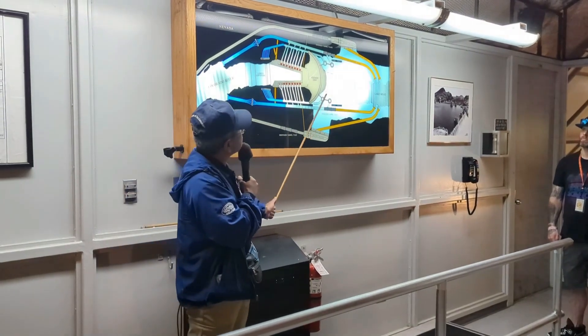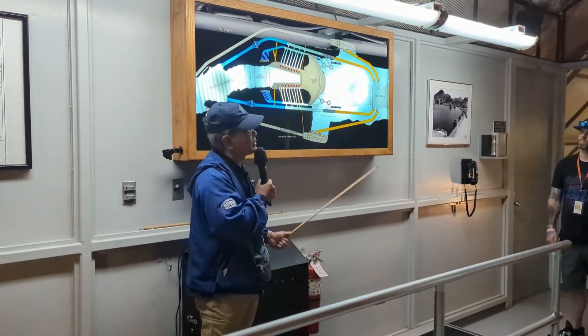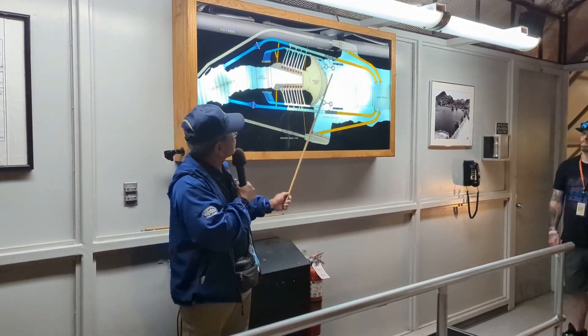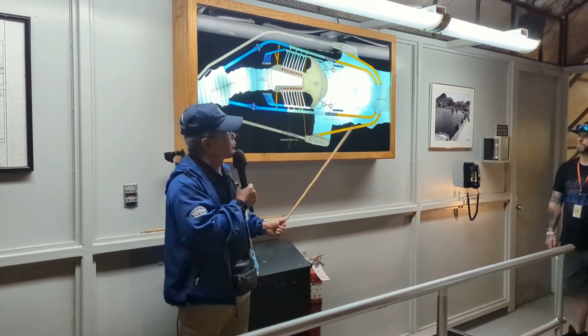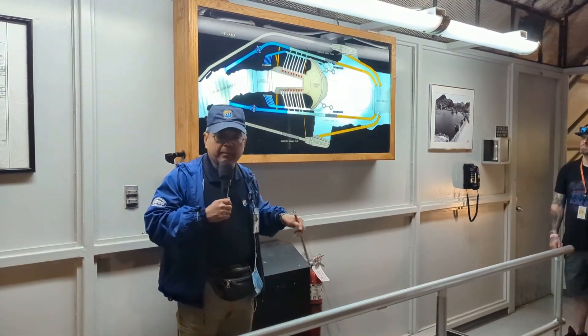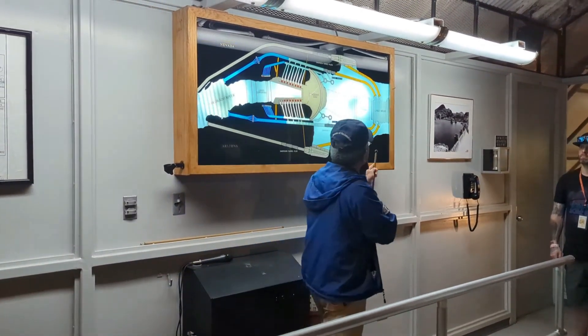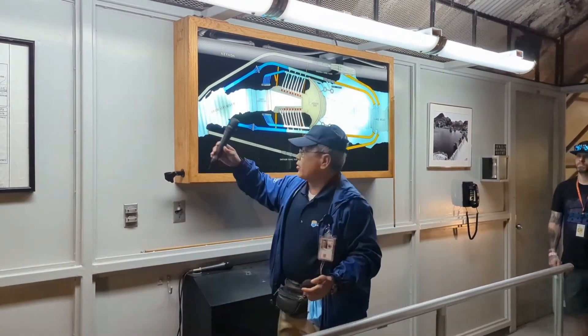The two inner diversion tunnels are linked to intake towers — those four large concrete structures you'll see when you're on top of the dam looking toward the lake. Each intake tower is 395 feet tall. Connected to them are 30-foot diameter penstock pipes that actively move water down from the lake to the power plant turbines. That pipe underneath us right now is one of those penstock pipes — the rumbling you hear is upwards of 96,000 gallons per second moving underneath us toward the power plant.